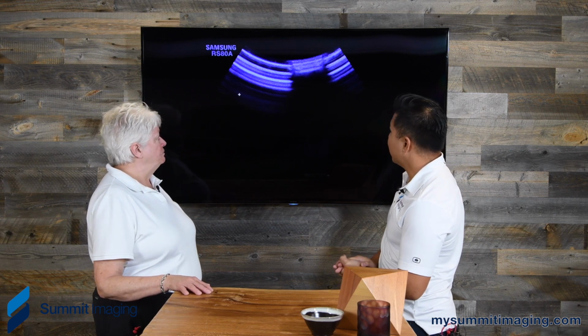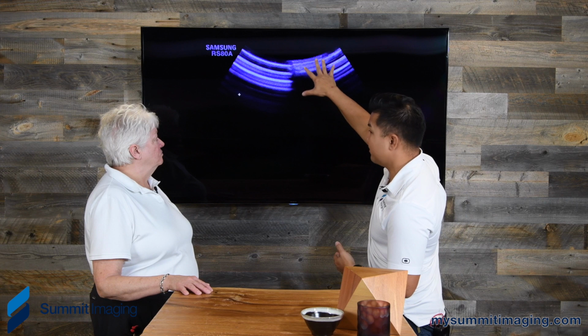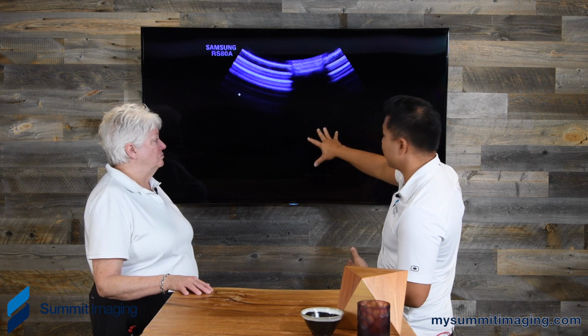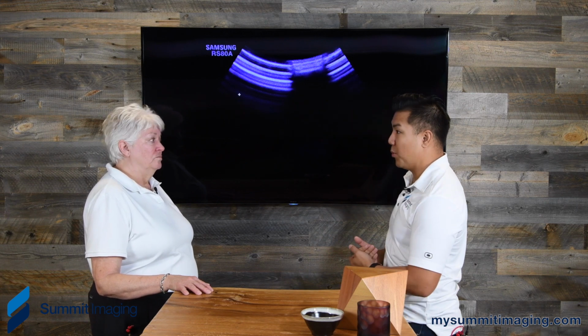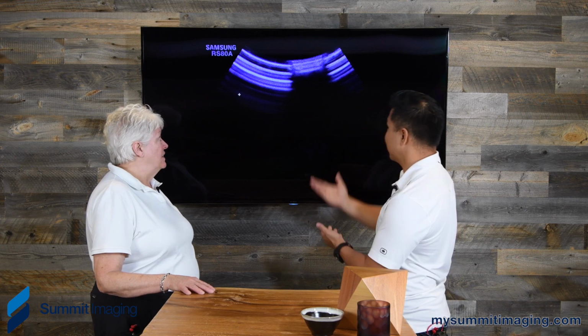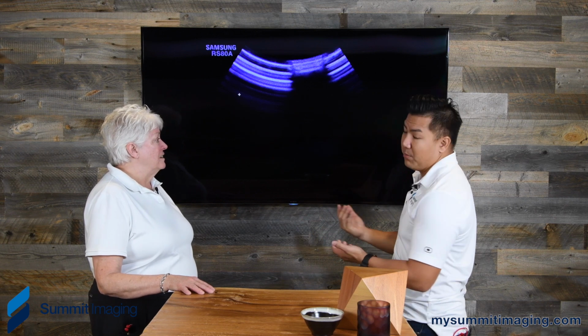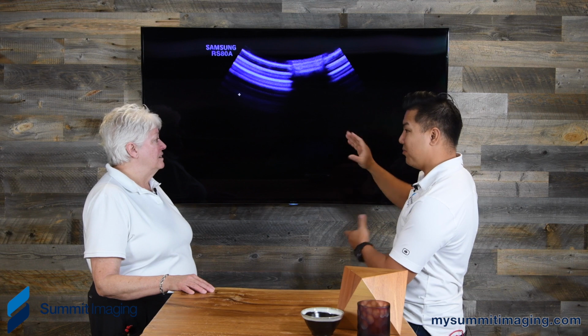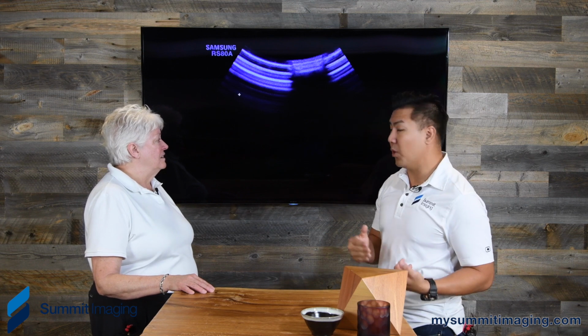Yeah, absolutely. My assumption is that because of the amount of missing data, that would probably be a probe that nobody would even want to use. Right, you're right at that point. This has to come in for repair, and we're able to go in and not only take out all the old oil, but put in new oil, replace all the seals and get those correct again, and restore the whole image for the customer.